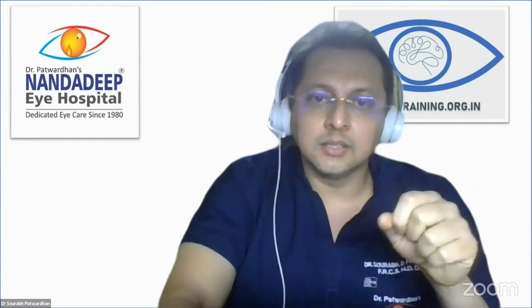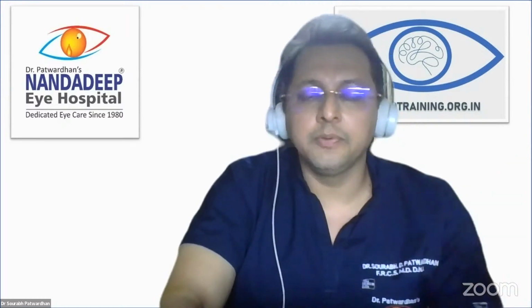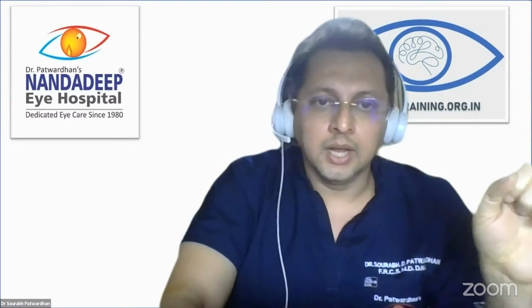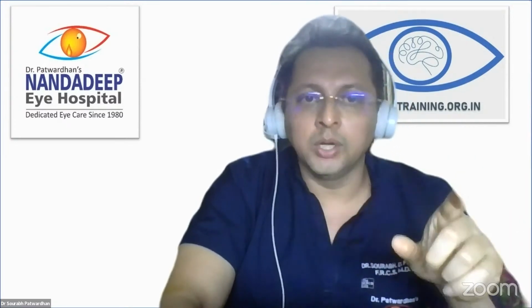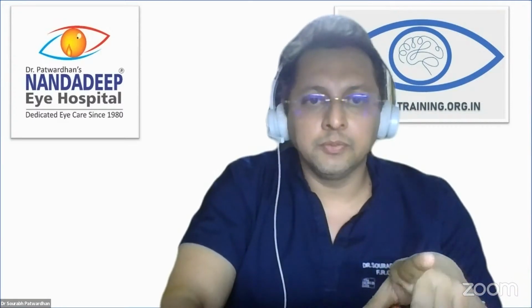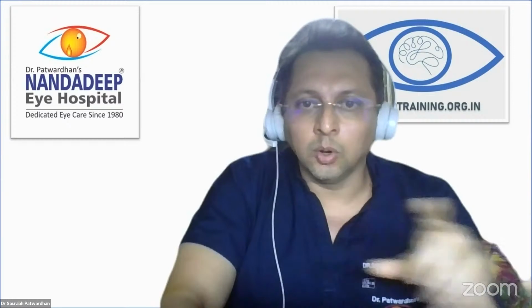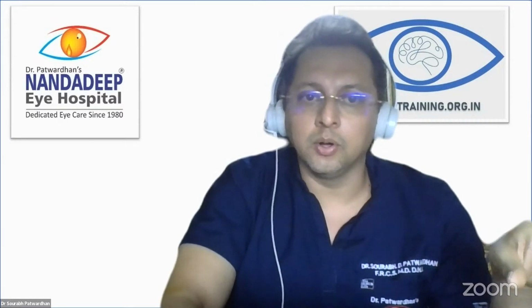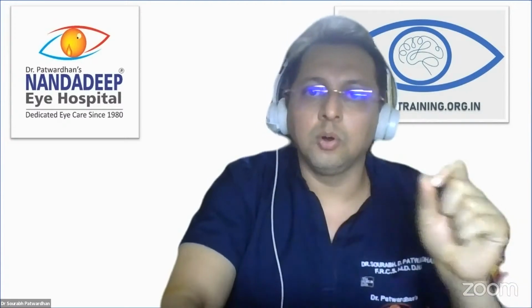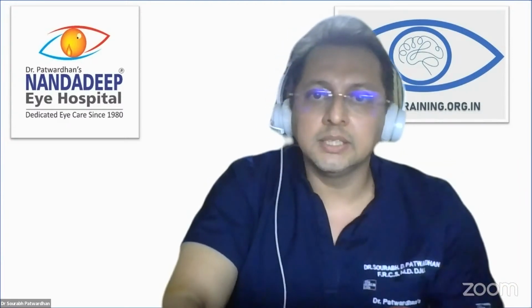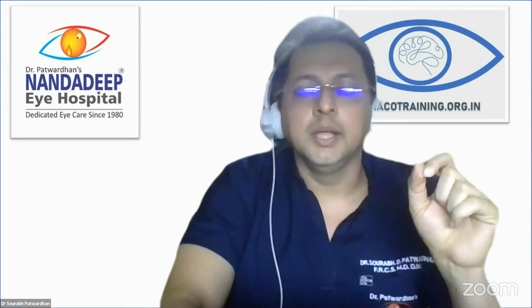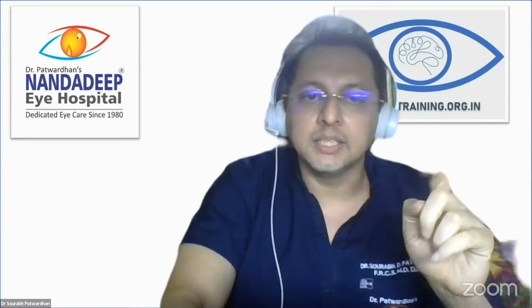In coastal areas, I think it's best to keep the dehumidifier on all 24 hours, not just in the OT but also in diagnostic rooms, because humidity breaks down a lot of electronic equipment in both OT and diagnostics. It's a very good tool to have in your OPD as well as OT, particularly in coastal areas and during the rainy season. Also, the first 6 to 9 months after installing a laminar airflow system, it has to be properly calibrated across all 3 seasons.